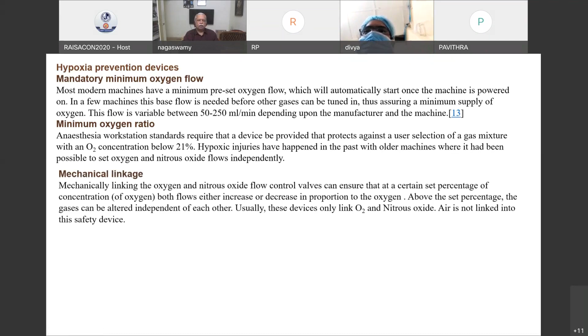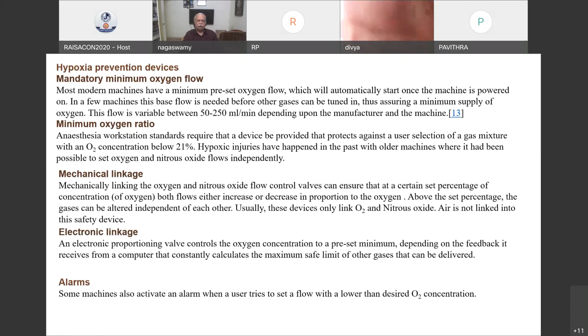And minimum oxygen ratio is another one, which is available for at least delivering more than 21%. And a mechanical linkage is there to connect nitrous oxide and oxygen so that a minimum of 25% oxygen is assured all the time. And with the modern electronic gadgets and flow meters, you have an electronic proportioning device, which also decides a preset minimum concentration of oxygen. And there are alarms to tell you when there is a low flow of oxygen or if the desired concentration is not delivered.